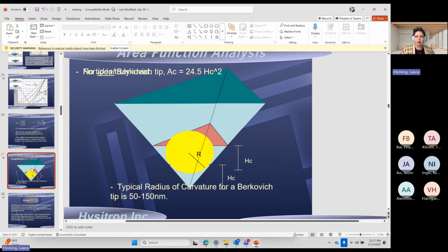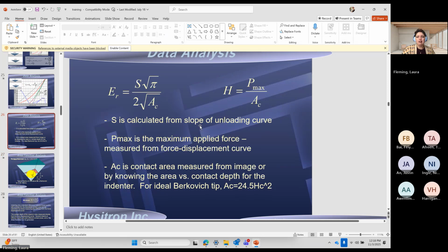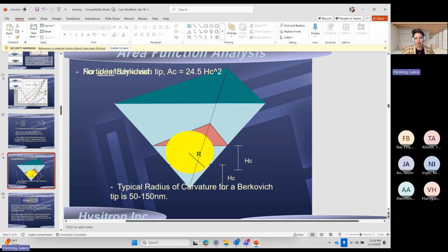However, we don't live in an ideal world. Of course not. It's nanoindentation. We're never going to have a perfect pyramid all the way down to the point. So there is some radius of curvature that occurs with any probe. And all of a sudden this idealized tip area function is no longer accurate, which means these results are no longer going to be accurate. So our hardness and reduced modulus results are only as good as our tip area function is.